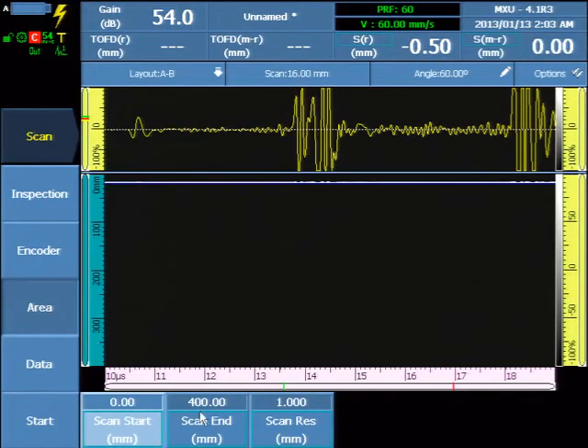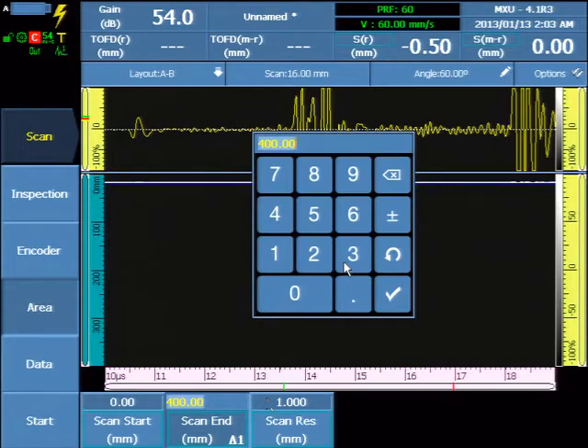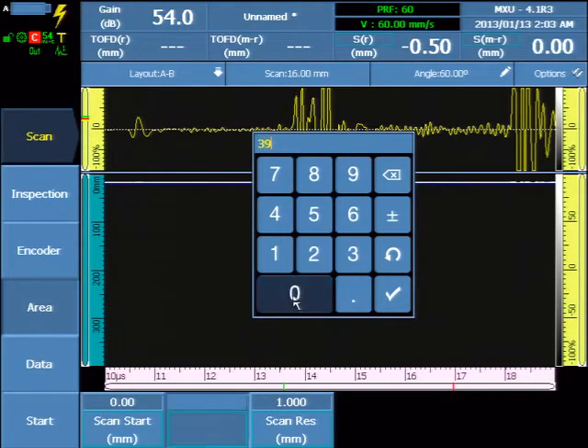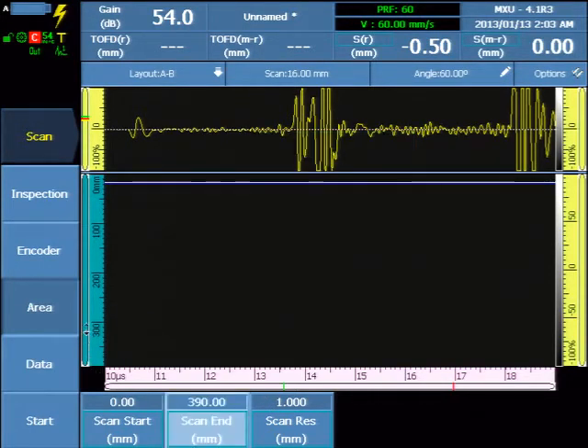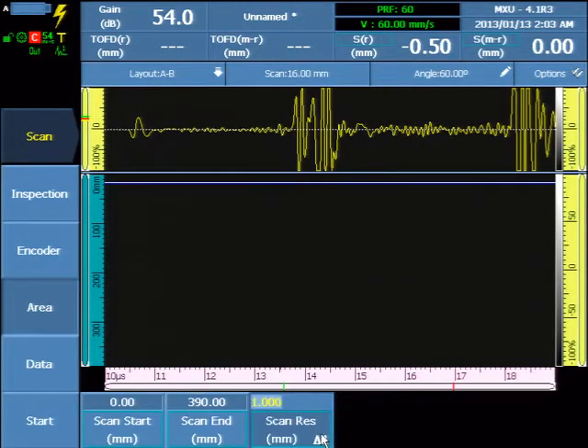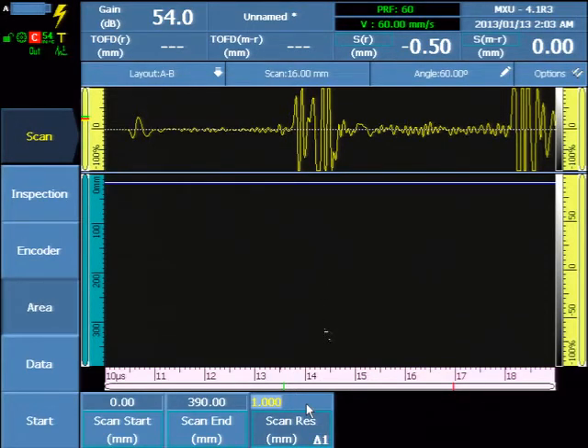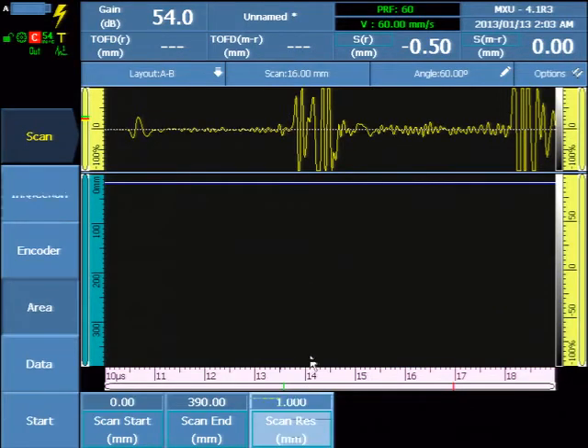Enter the area or distance for the inspection. This is the total length of the blue scan axis ruler on the display. And the scan resolution. The scan resolution is the interval at which the A-scan is collected as the scanner is moved. And in a 1 millimeter resolution is typical, resulting in plus or minus 2 millimeter length sizing.